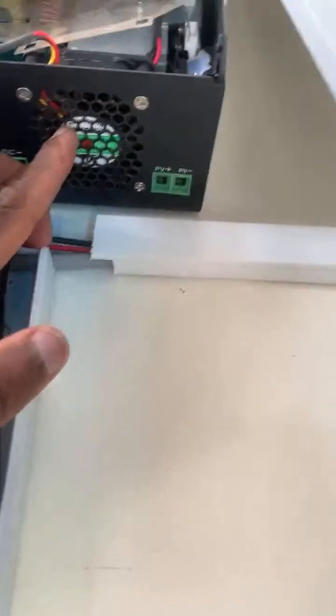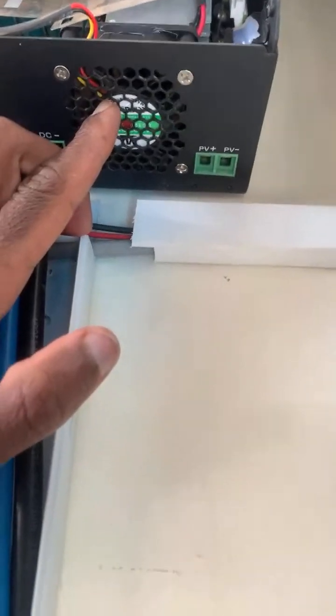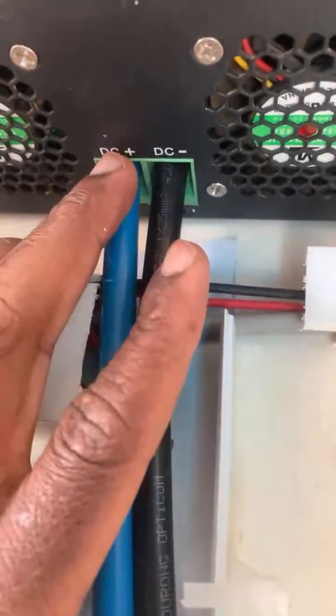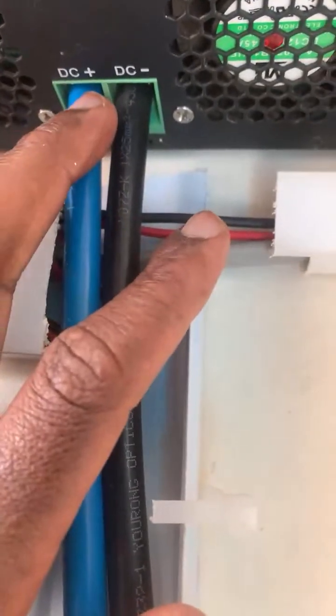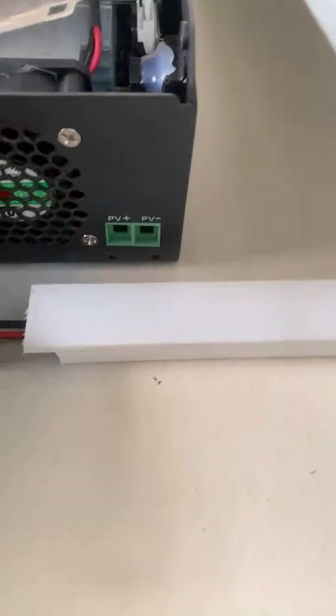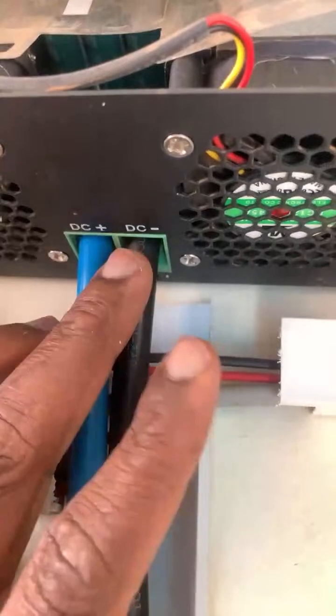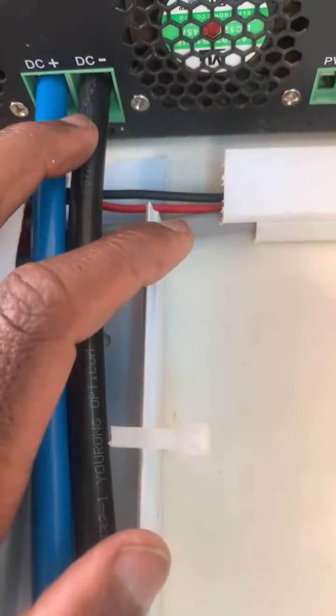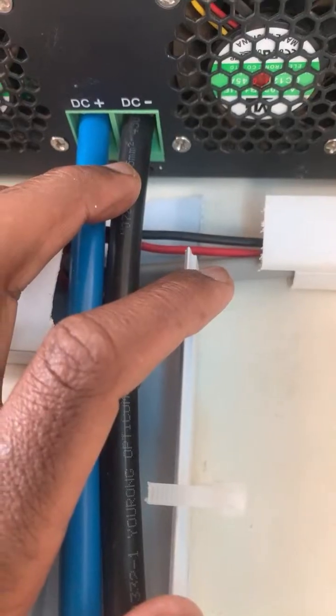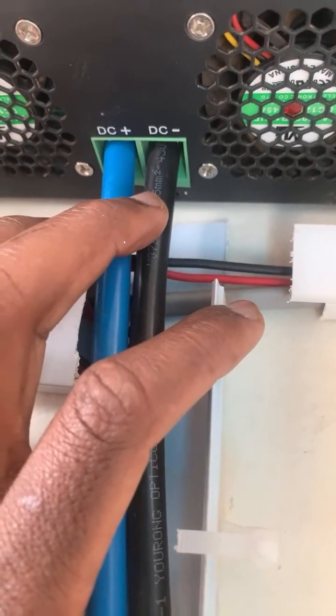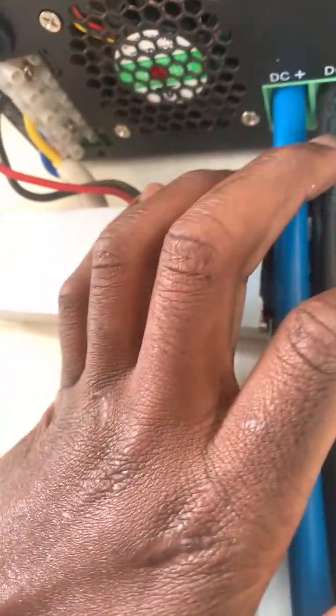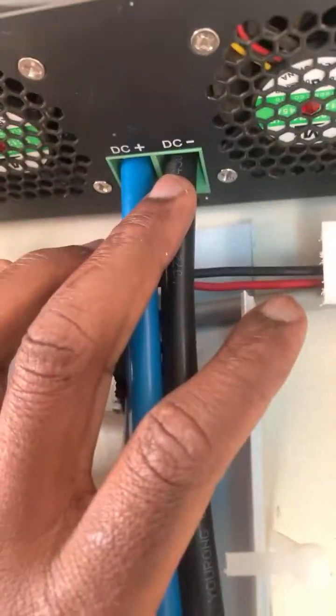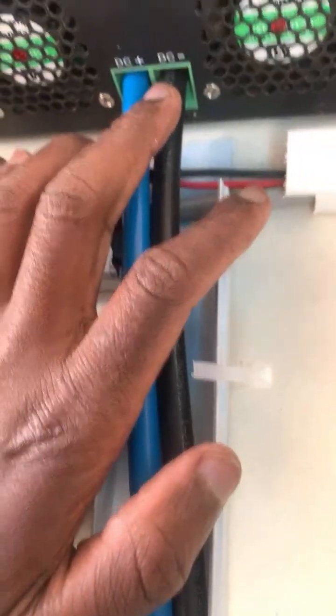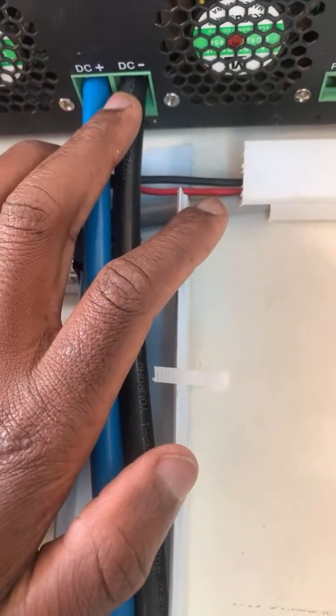This is definitely the fan cooling system, right? And then we have DC. Now this is the connection for the battery. Notice how different it is, very huge compared to the PV, because it has to have minimal resistance. Another important thing, it has to accommodate the size of the cables, because DC requires larger size cables.